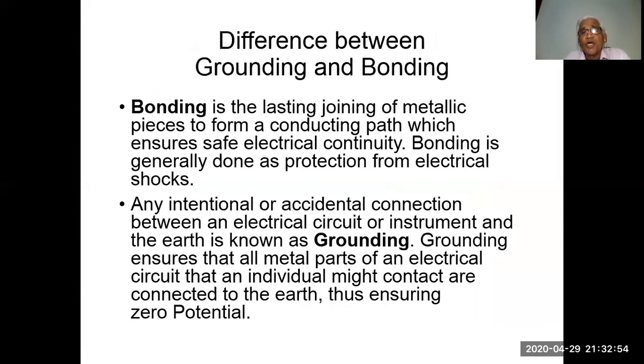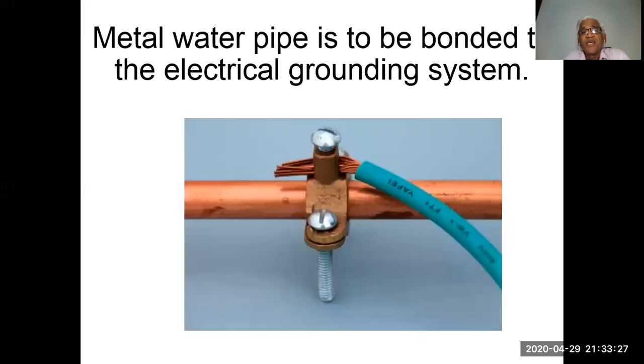The difference between grounding and bonding. Bonding is the lasting joining of metallic pieces to form a conducting path which ensures safe electrical continuity. Bonding is generally done as protection from electrical shocks. Any intentional or accidental connection between an electrical circuit, instrument, and the earth is known as grounding. Grounding ensures that all metal parts of an electrical circuit that an individual might come in contact with are connected to the earth, thus ensuring zero potential. A metal water pipe is to be bonded to the electrical grounding system, as you can notice in this figure.